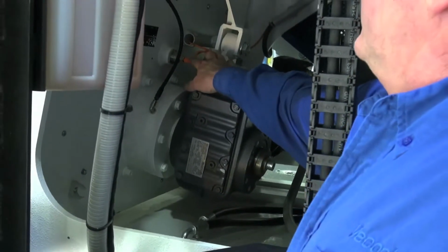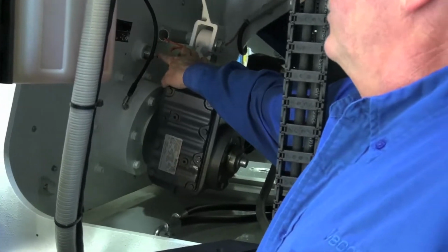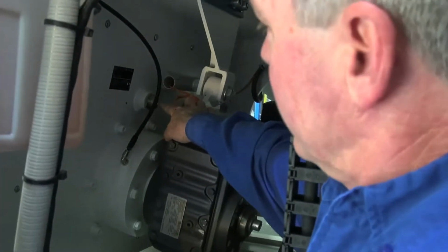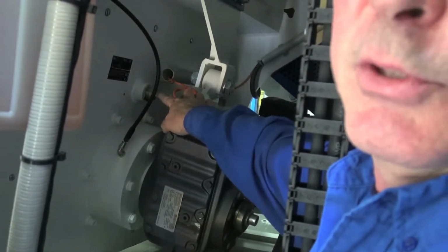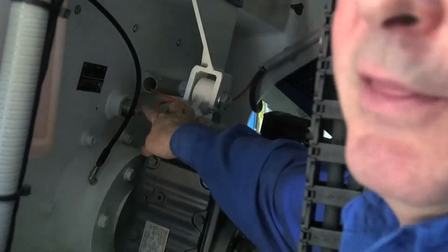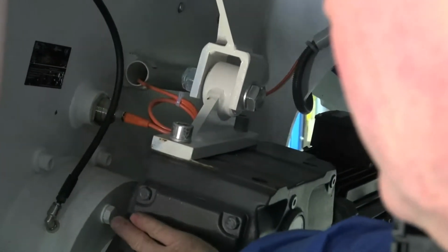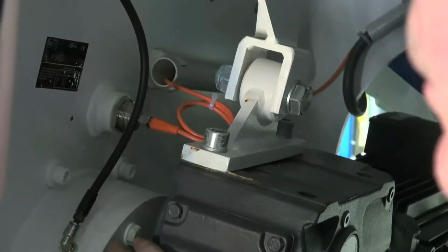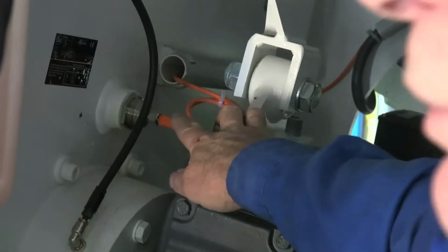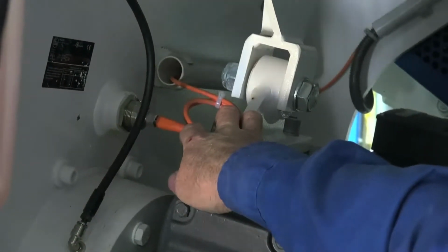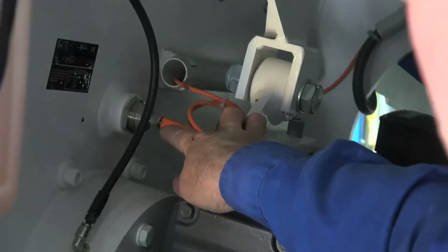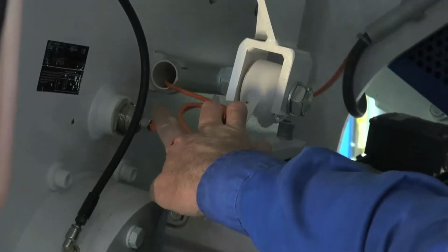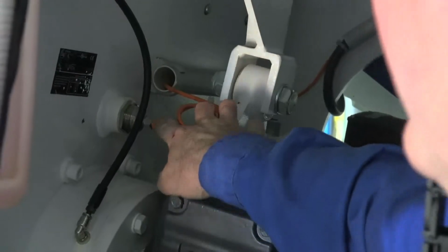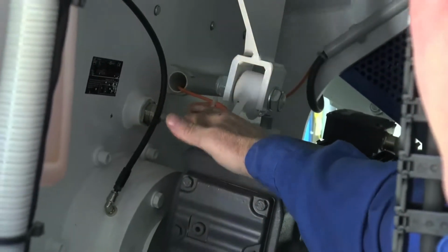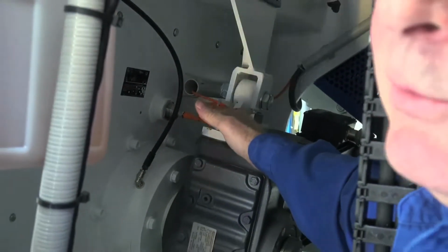One thing to note back here in this area is this photo sensor. That photo sensor recognizes that the auger is turning. We put that there so that if there is a problem with a gearbox or a shaft on the auger and it stops turning, this sensor will give you a fault on your HMI and will shut the machine down. We'll not let the machine run unless we get a pulse from this sensor every so often. We're going around to the screen now. We'll show you that sensor from the inside.